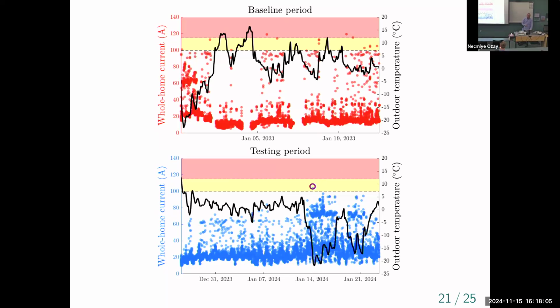This was just the real-time control layer, the if-then logic that turns things off if you get too close to the 100 amp limit. You might ask whether that control layer was enough, whether we really needed all this sophisticated machinery for the MPC. We found that this failed because our real-time control layer would check if we're getting close to 100 amps and start turning things down and eventually off the closer we got to violating that constraint, but it had no predictive logic in it.